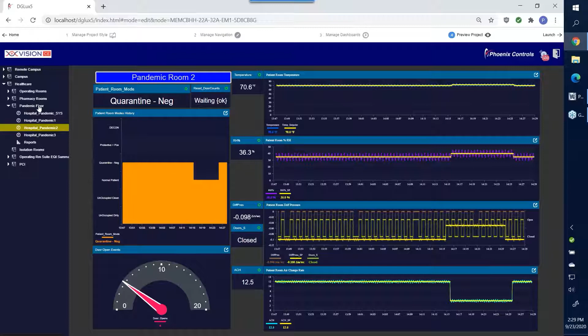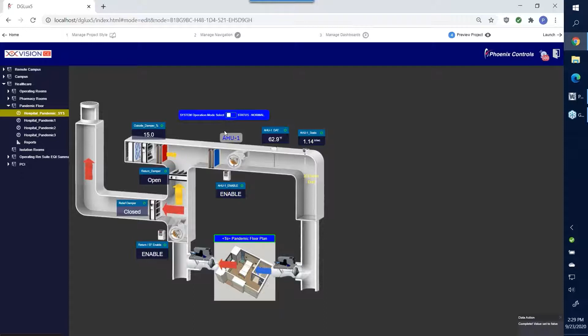And this is the approach that you would take to make sure that we went from a quarantine mode into a dirty mode, so that there would be a process and a procedure to make sure that, as you can tell right here, these rooms now have no patients because nobody has cleaned those rooms yet. We would go back over here to the system operation and adjust this into your normal mode, damper switch. We're now back to a standard air handling unit. As you would expect, once these rooms have been cleaned, we would then go back and set these up to now an unoccupied clean.